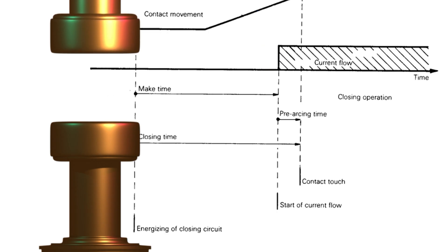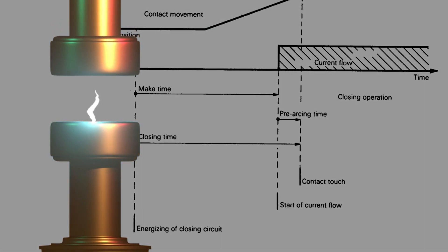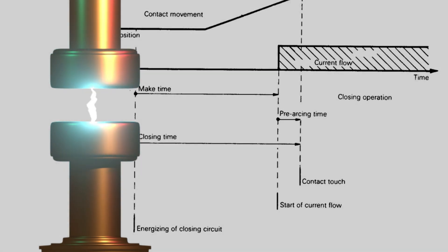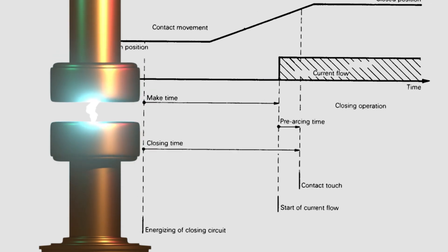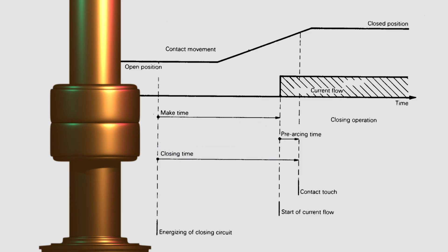As the moving contact approaches the fixed contact, but just before touching, an arc initiates due to the high voltage gradient across the very small gap between the contacts. This high electric field causes the dielectric medium between the contacts to break down, resulting in arc initiation. As the arc is initiated, current starts to flow through the breaker, even though the contacts have not yet physically touched. Shortly after that, the contacts physically touch and the current continues to flow normally. The time from when the closing circuit is energized to the arc initiation is called the making time.